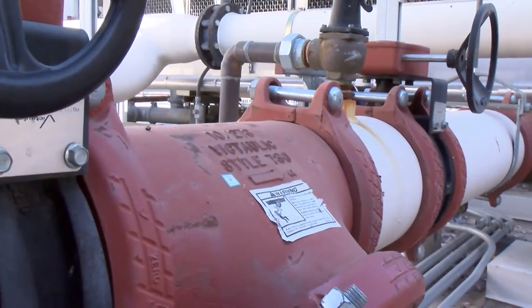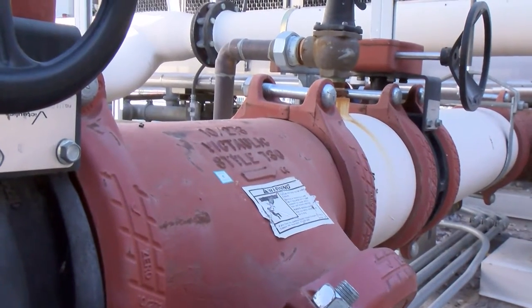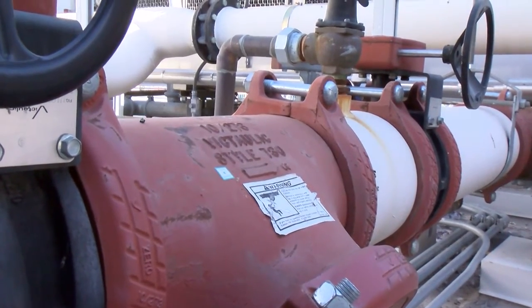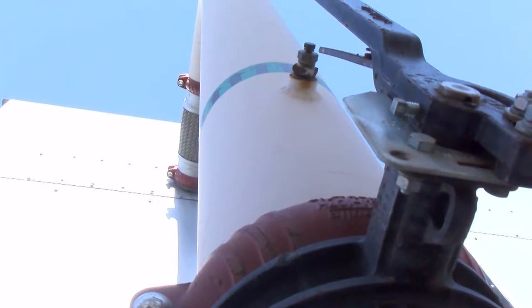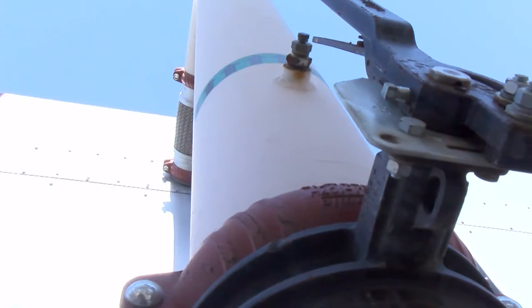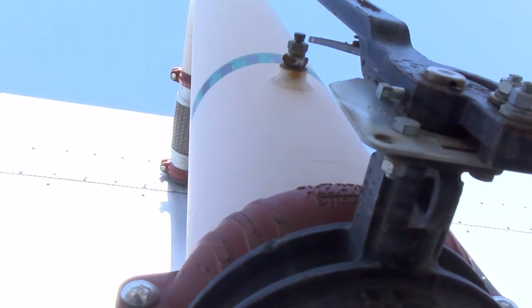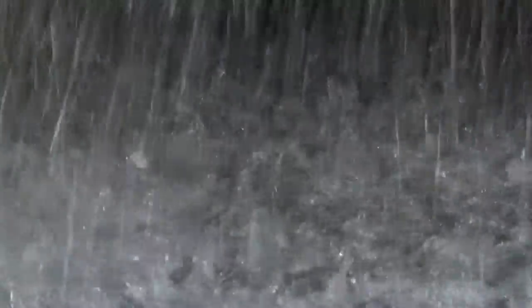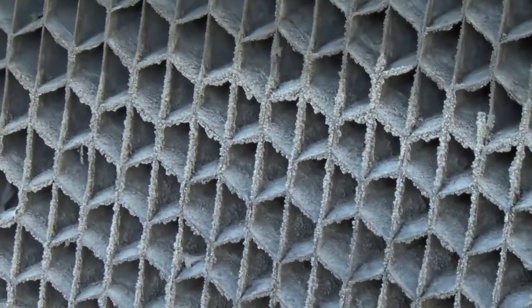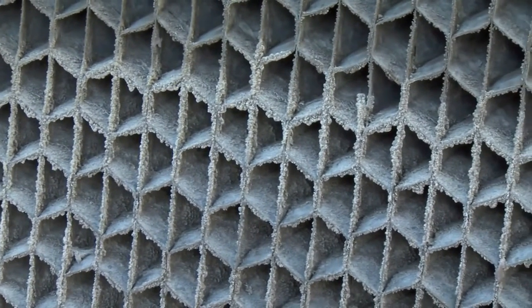Is the goal of the modifications to decrease the number of times the system needs to be flushed of water? Well, that's a good point. One problem with using a cooling tower system is that over time the water gets hard—hard enough that it can damage the equipment. Part of the strategy for dealing with the hardness is to add chemicals. On top of that, over time it starts to concentrate, and it gets so hard that it needs to be flushed from the system. So water does get flushed periodically, and it's made up with the drinking water that we use.